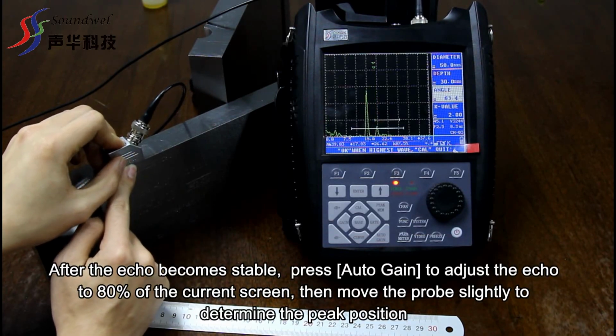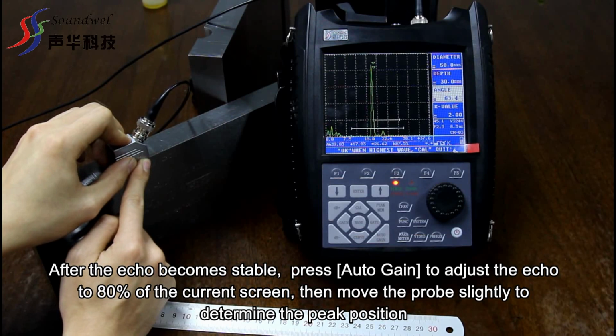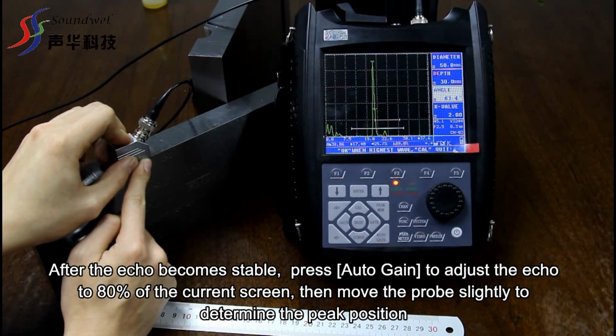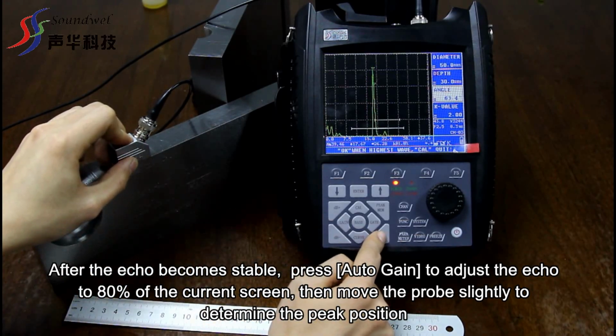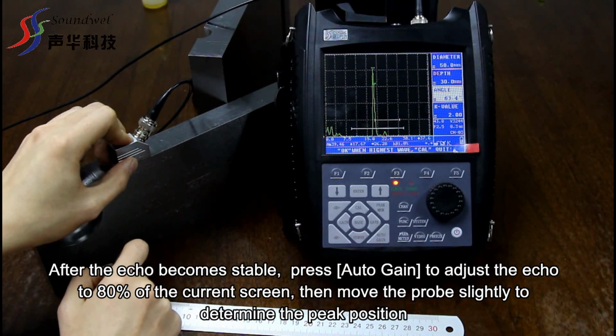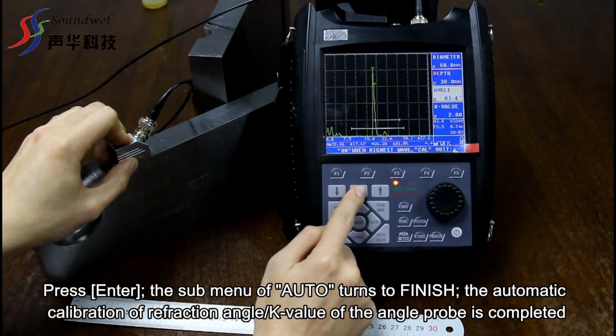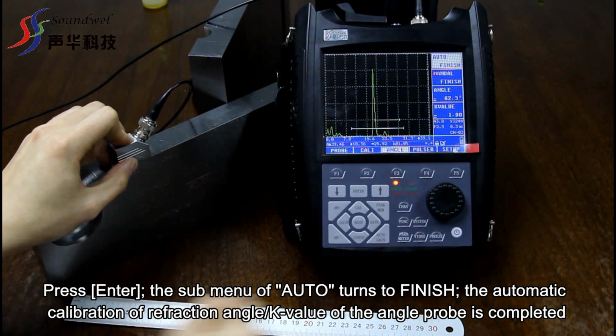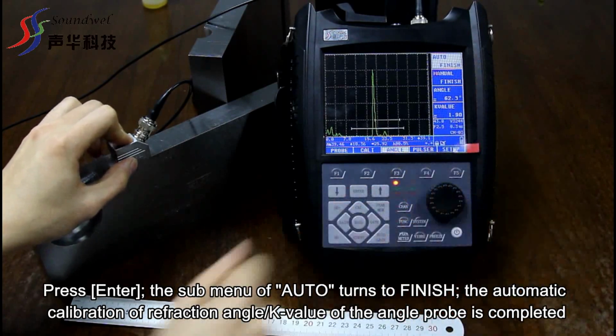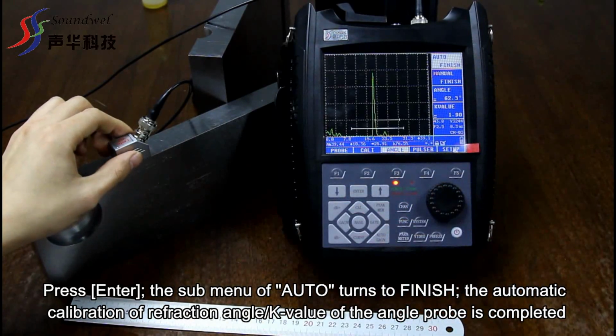After echo becomes stable, press Auto Gain to adjust the echo to 80% of the current screen. Then move the probe slightly to determine the peak position. Press Enter. The submenu of Auto turns to Finish. The automatic calibration of refraction angle K value of the angle probe is completed.